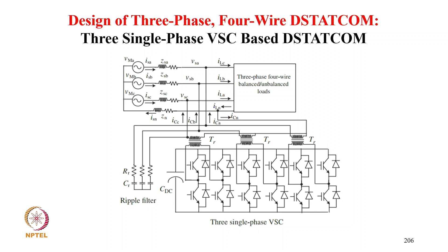So design parameters of DSTATCOM. DSTATCOM is designed for compensating a reactive power of 50 kVA with a safety factor of 1.1 in a 415 volt 50 Hz three-phase distribution. DSTATCOM rating is 50 kVA. AC line voltage for 50 Hz, VSP equals VLL upon root 3, which is 239.6, and safety factor 1.1. So the I DSTATCOM is 1.1 times S upon root 3 VLL. So that comes 76.516 ampere.